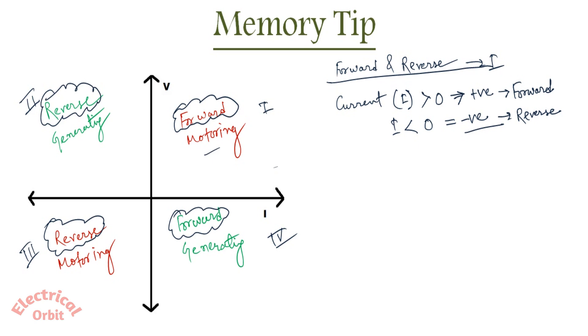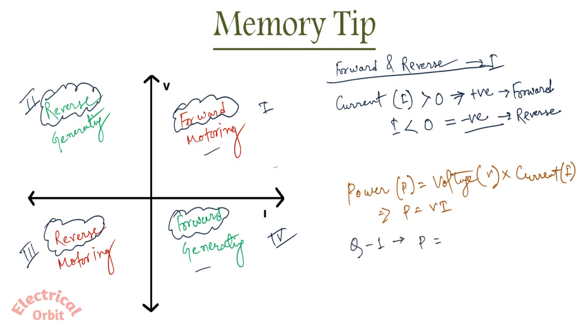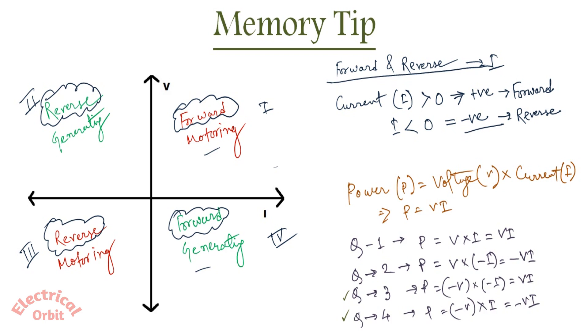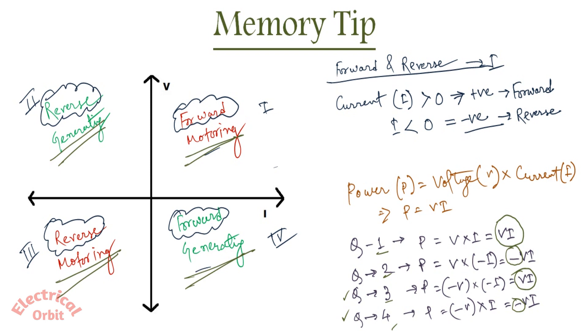Next, for motoring versus generating — we know power equals voltage multiplied by current. For quadrant 1 your power is positive: plus V times I. For quadrant 2 voltage is positive but current is reversed, so it is minus V times I. Similarly for quadrant 3 and 4. Whenever V times I is positive — quadrant 1 and quadrant 3 — it's motoring; whenever your power is negative — quadrant 2 and quadrant 4 — it is generating.